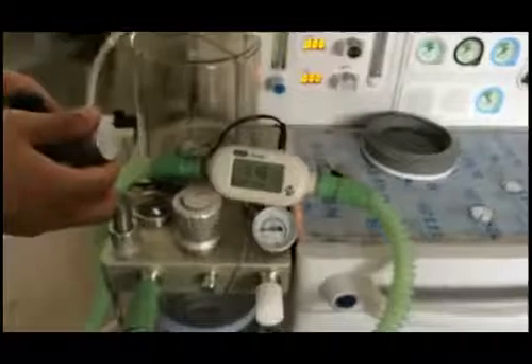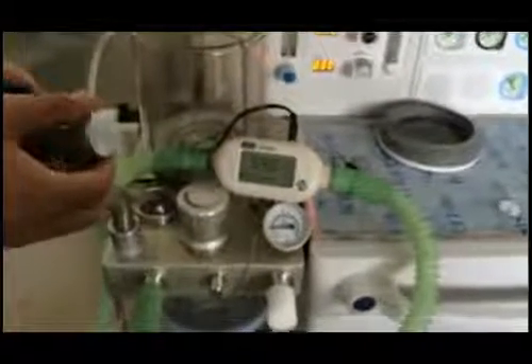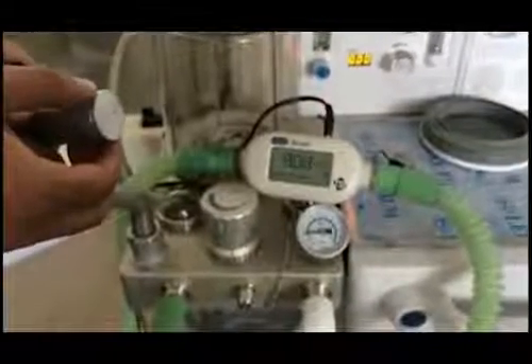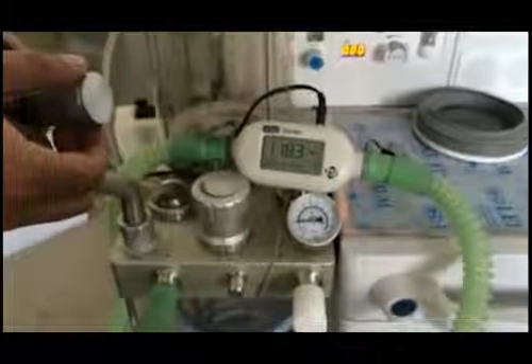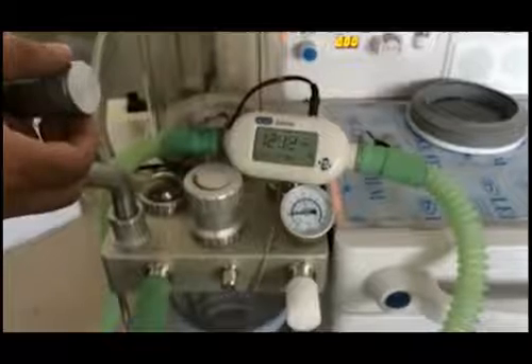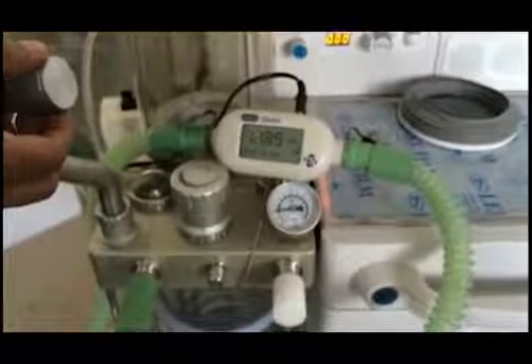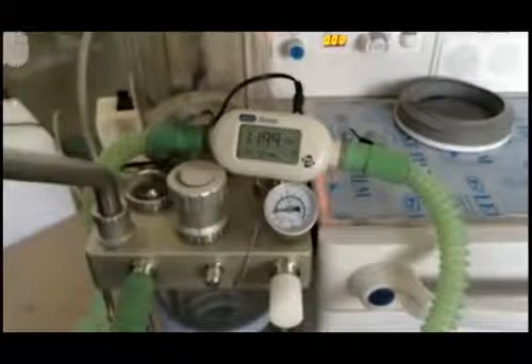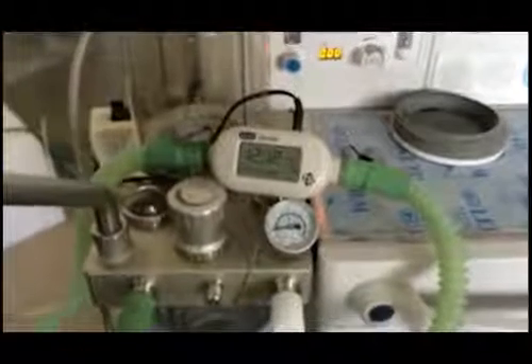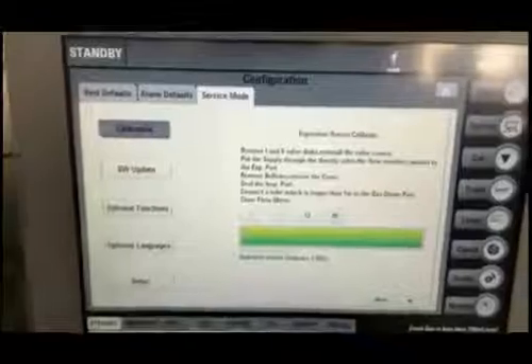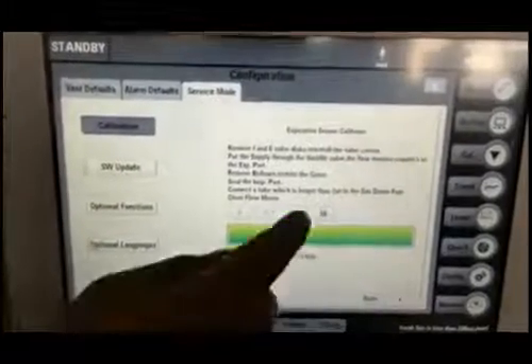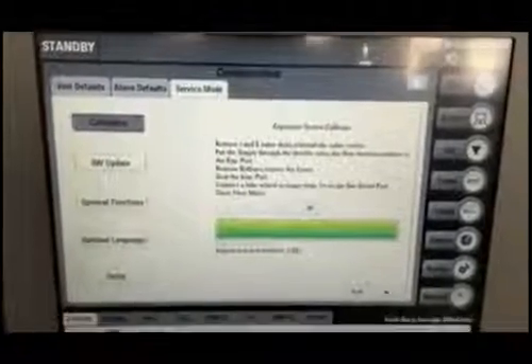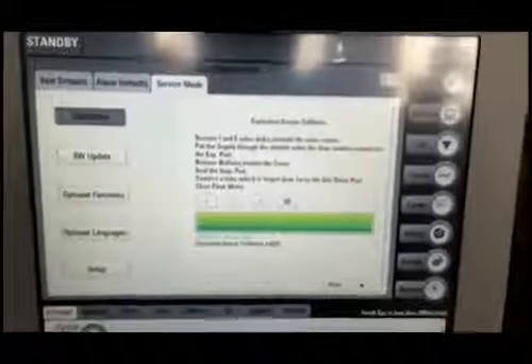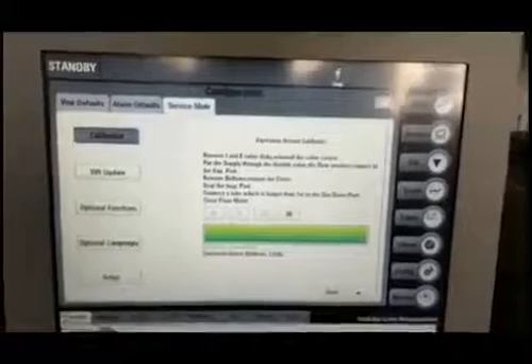Please look at the flow meter. Now rotate the throttle. After the value 12 has been reached on the flow meter, please press the key displayed on the screen. After the calibration is successful, the calibration successful sign will be displayed. Now we will perform the calibration for 30 liter per minute.